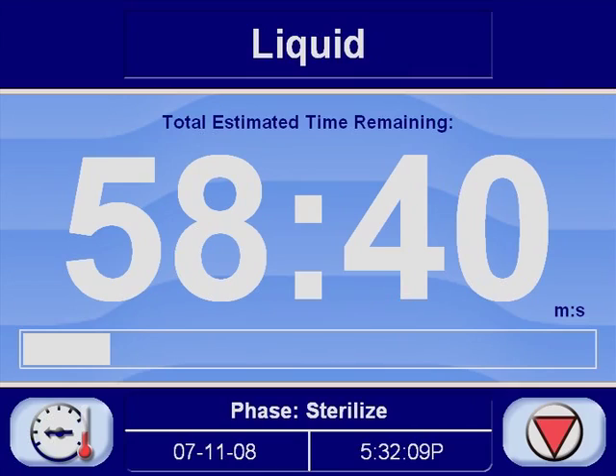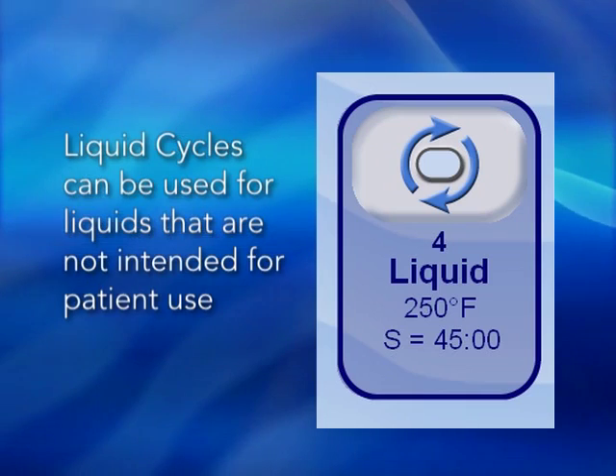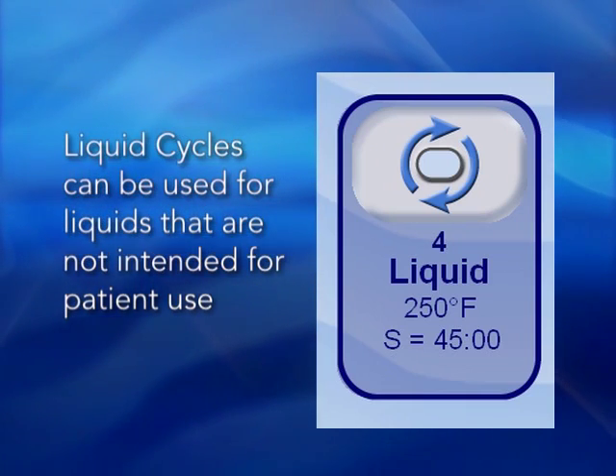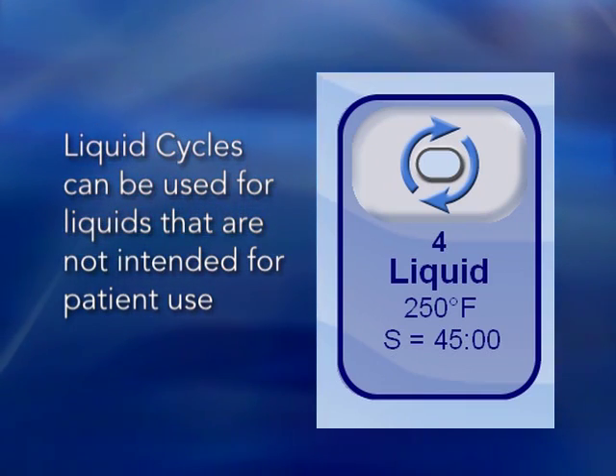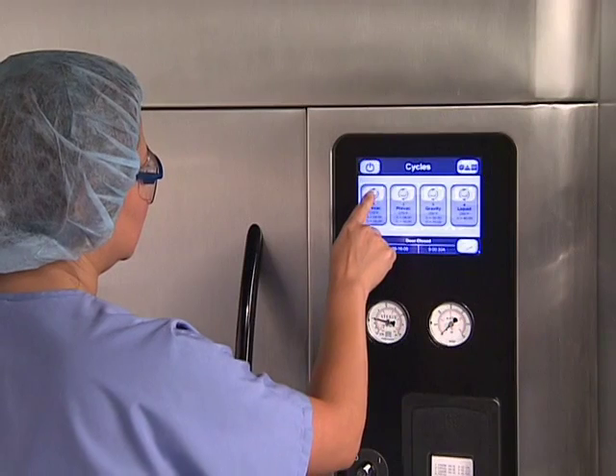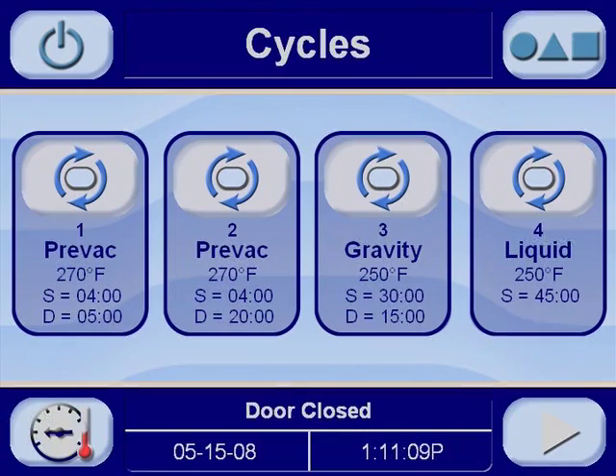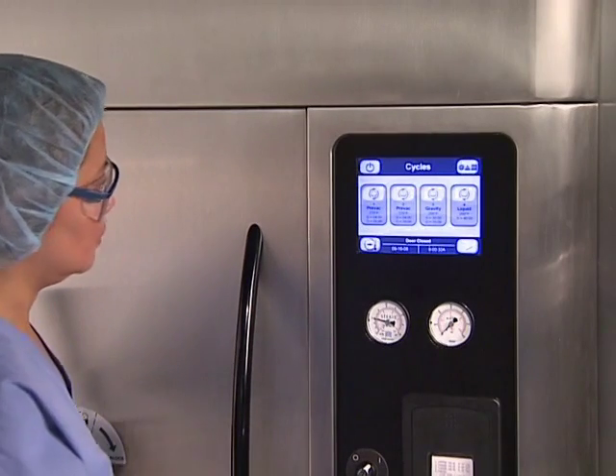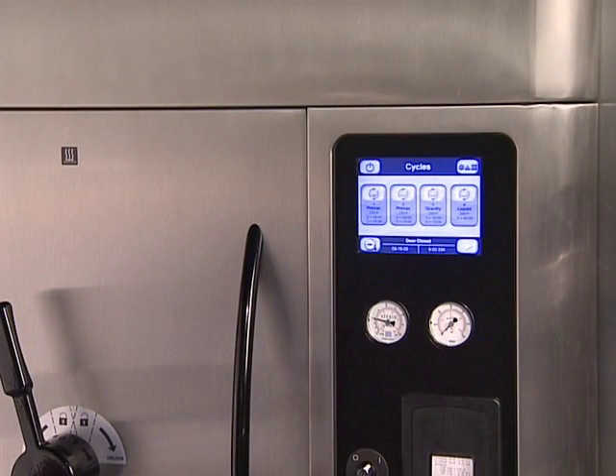If Prevac cycles are run on an SFPP sterilizer, you should perform a Bowie Dick test. The liquid cycle may be used to sterilize fluids that are not intended for patient contact. Up to 3 containers, each holding 1,000 milliliters of liquid per container, may be sterilized. To initiate a cycle, press the desired cycle button. A steam-activated door seal secures the door. The sterilizer automatically progresses through the cycle.